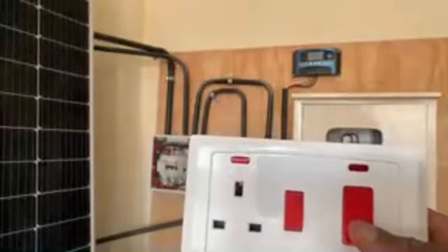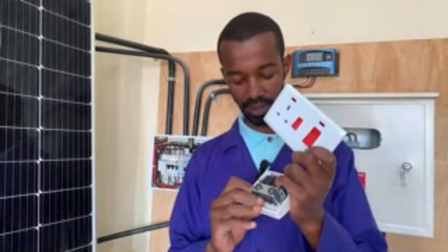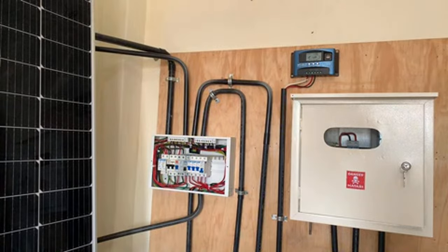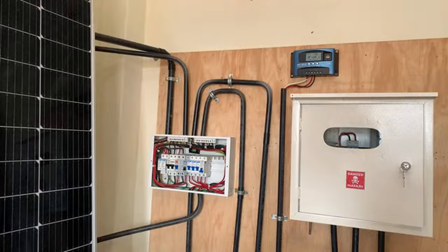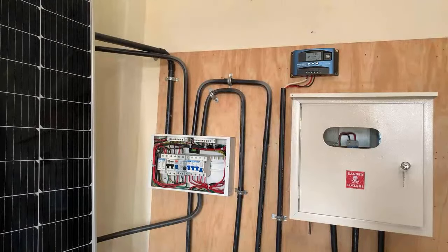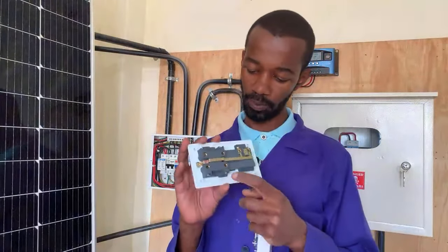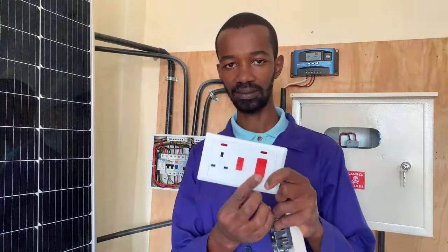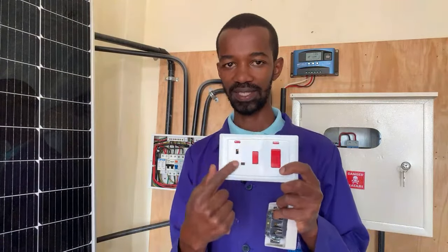So if you are connecting your cooker connector, which is definitely this one, it is normally connected below the cooker unit. So you ensure that the output from this double pole here goes all the way to the cooker connector, so that your customer's electric cooker is connected to the cooker connector. So from the input of this DP switch here, where we have this heavy gun, you also have the supply of this single socket here.